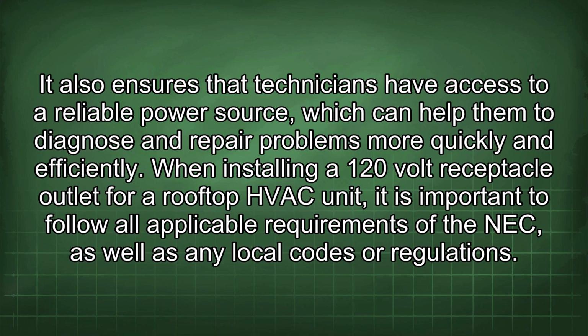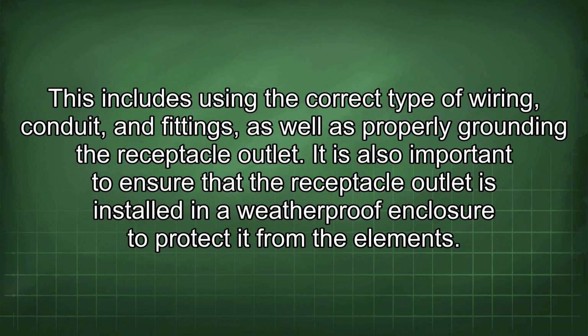When installing a 120-volt receptacle outlet for a rooftop HVAC unit, it is important to follow all applicable requirements of the NEC, as well as any local codes or regulations. This includes using the correct type of wiring, conduit, and fittings, as well as properly grounding the receptacle outlet. It is also important to ensure that the receptacle outlet is installed in a weatherproof enclosure to protect it from the elements.